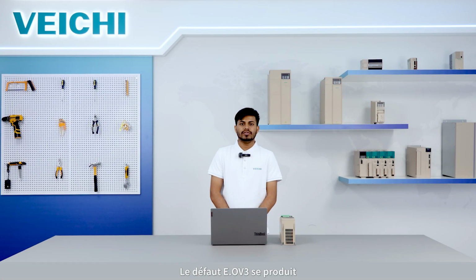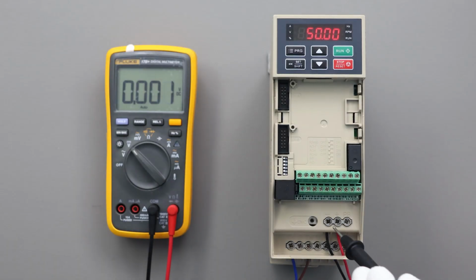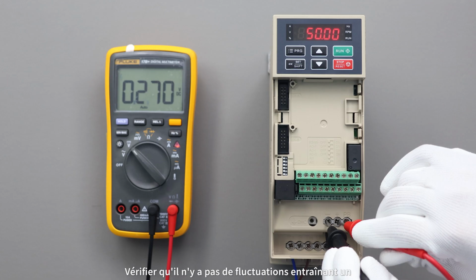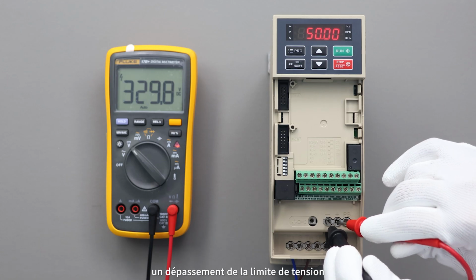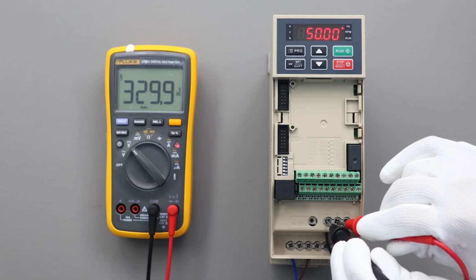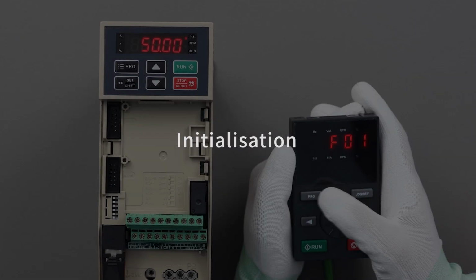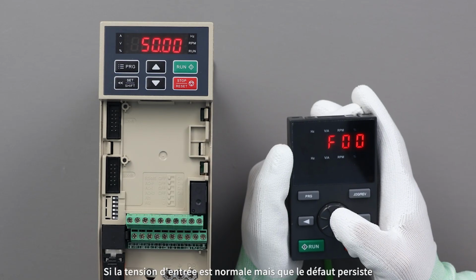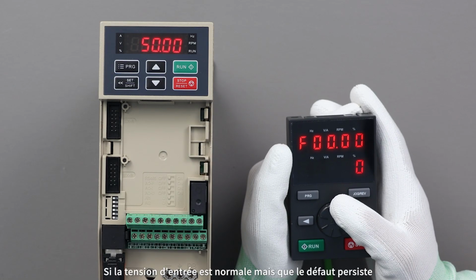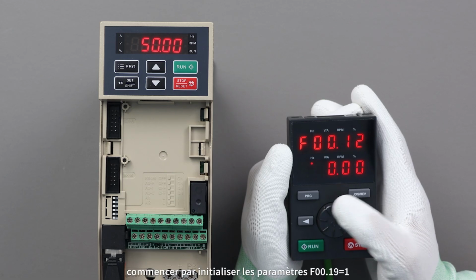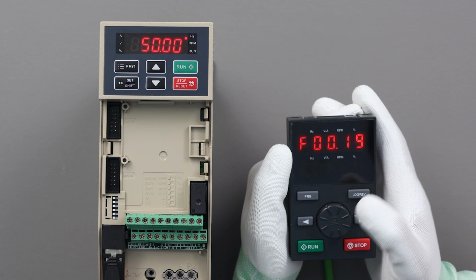The E.OV3 fault occurs when the bus voltage exceeds the maximum allowable value during the constant speed operation. Measure bus voltage. Verify if there are any fluctuation causing the voltage exceed the limit. Initialization. If the input voltage is normal but the fault persists, start by initializing the parameters F00.19 to 1.